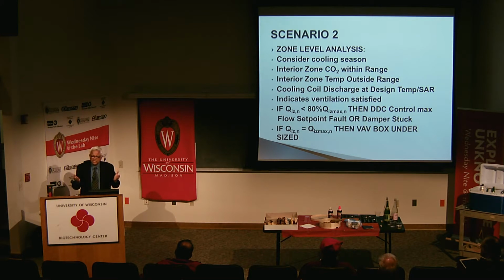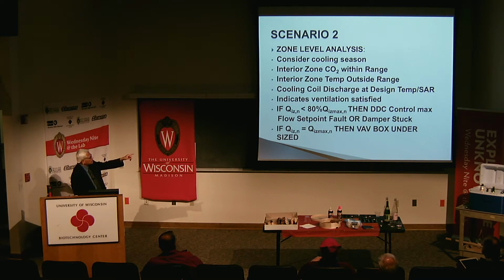If the temperature is not satisfied, you want to make sure whether the flow coming into the room or the occupied zone is at 100% or not. If it is not 100%, there is a controller which keeps repeatedly changing the set point at different flow rates. If it's a full load, it should really set it to 100%. So that means the fault is with the DDC control not setting the maximum flow set point. Or, as I mentioned, the variable air volume box has a damper blade which modulates the hot and cold air, and during the cooling season it should open completely to the cold air. Maybe the damper blade is stuck. If it is stuck, you don't have enough air coming through.